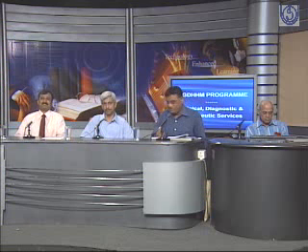Thank you. Actually, the total life of medical equipment is around 7 to 10 years, especially costly equipment like CT scans and MRIs. You can make out the life of the equipment from what the manufacturer gives you, that this much AMC is possible for 5 years or 7 years. That itself gives you a clue to the life of the equipment, because beyond that it will be very uneconomical for a manufacturer to give spares as well as maintenance and warranty. That is my view. Thank you, Colonel Rao.